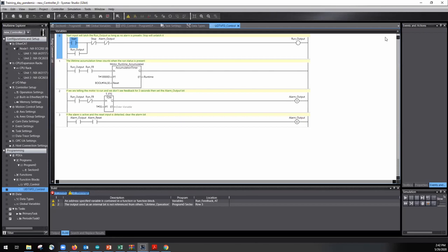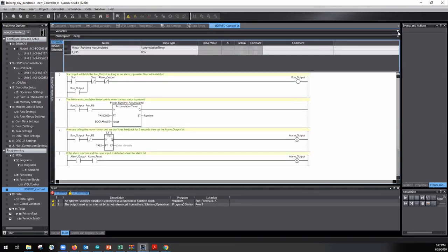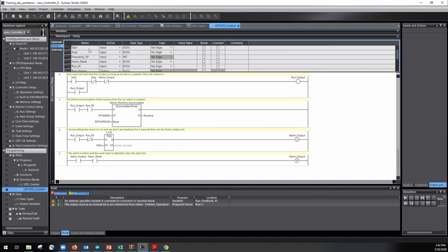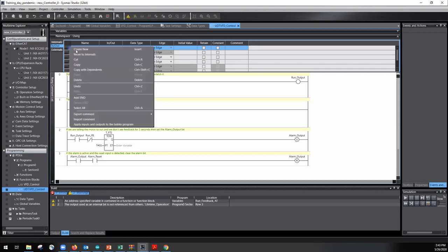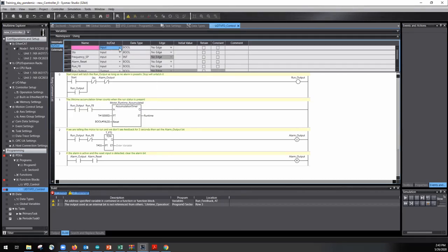Now let's open that up. Expand our variables at the top. Now on our in-out variables, we are actually just going to have one variable. We'll create a new one. It's going to be an in-out variable. This is where we use the in-out variable, because that UDT that we're bringing in has both inputs and outputs in it. So we need to be able to read and write from that chunk of data and just pass it through the block. So we're going to use the in-out parameter.